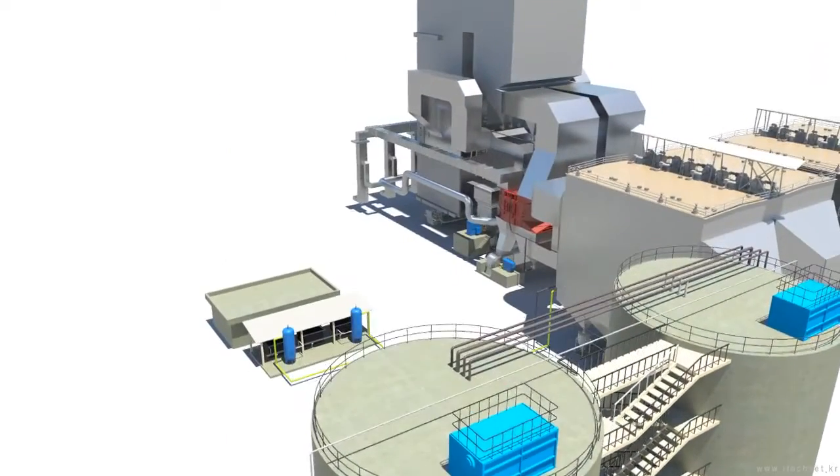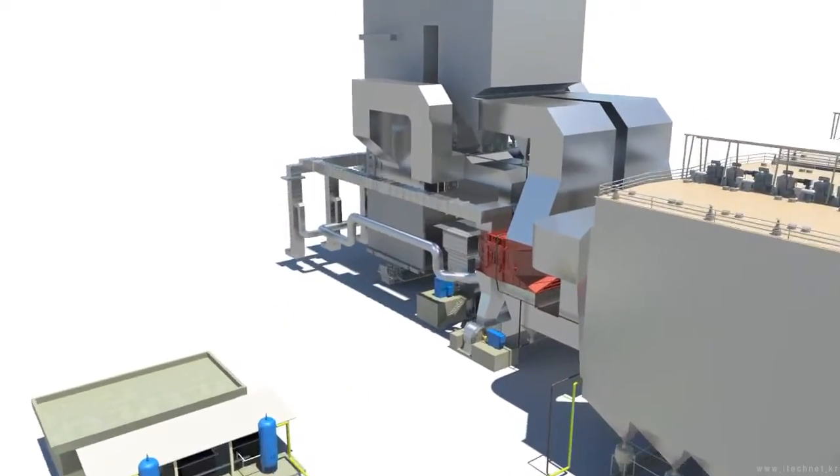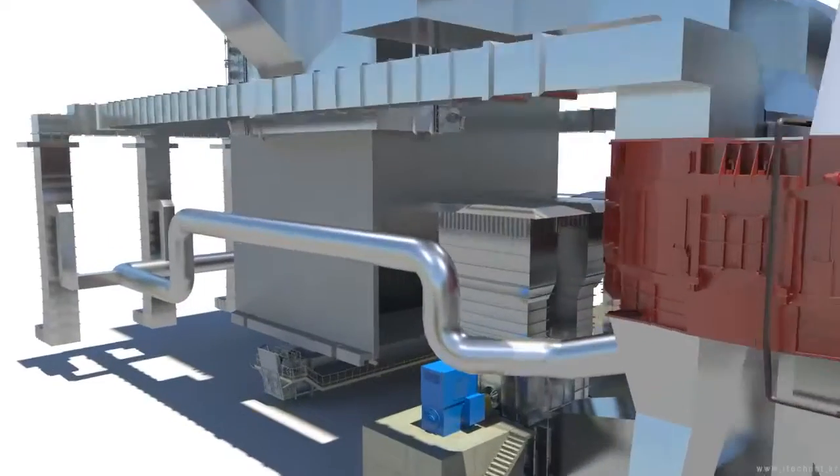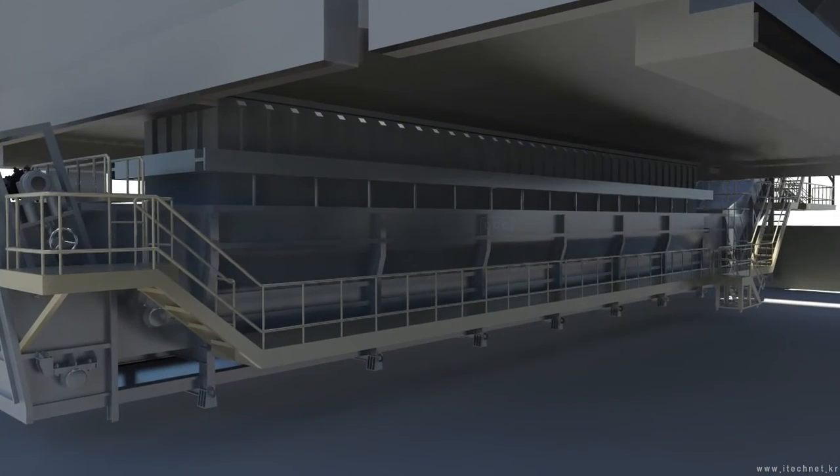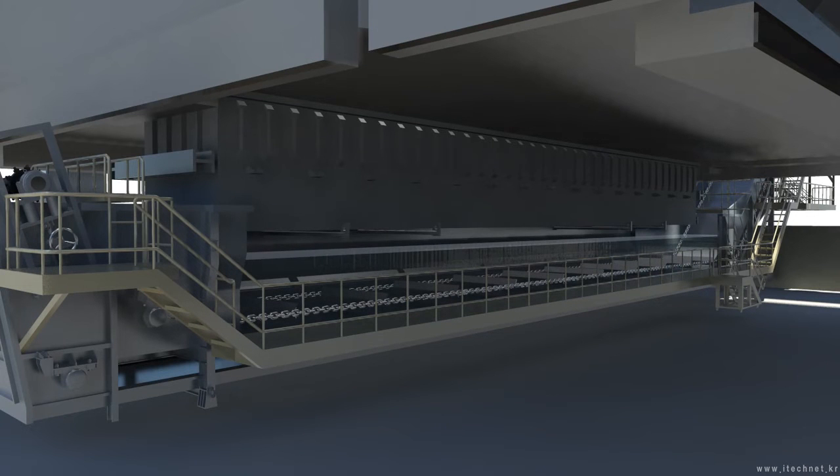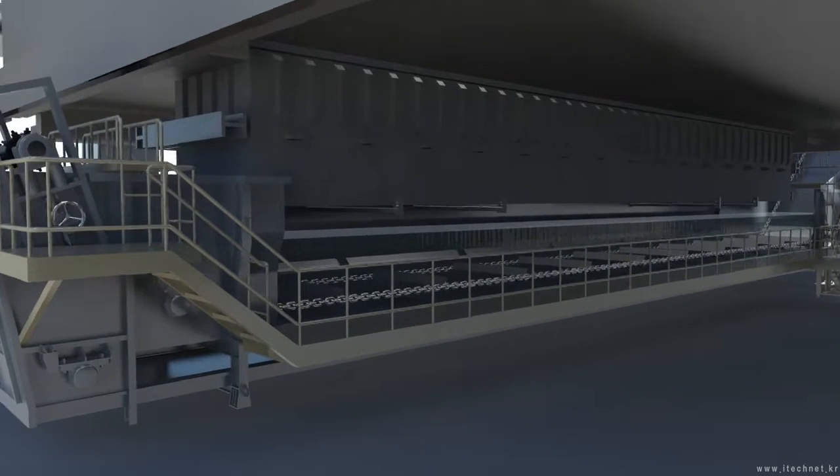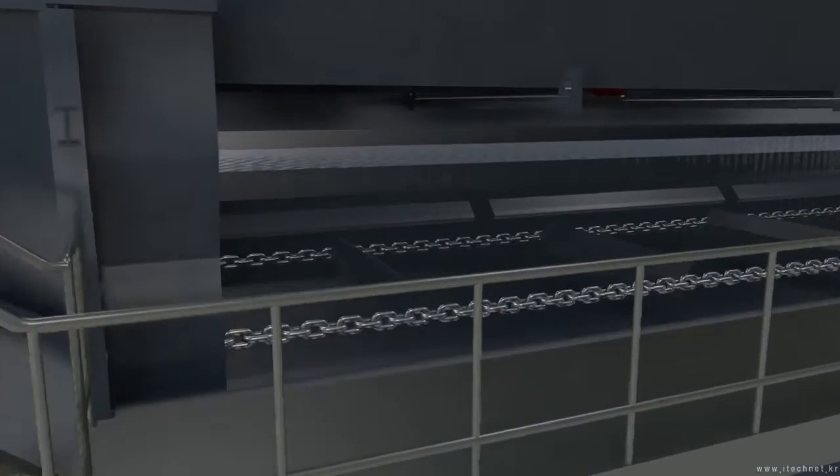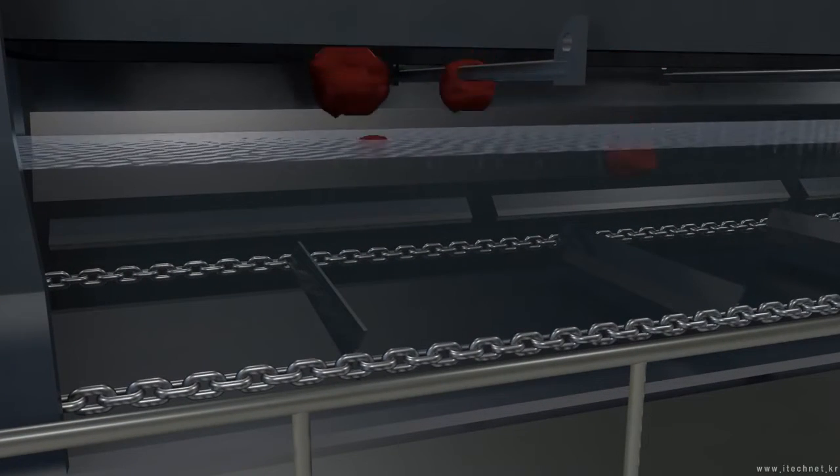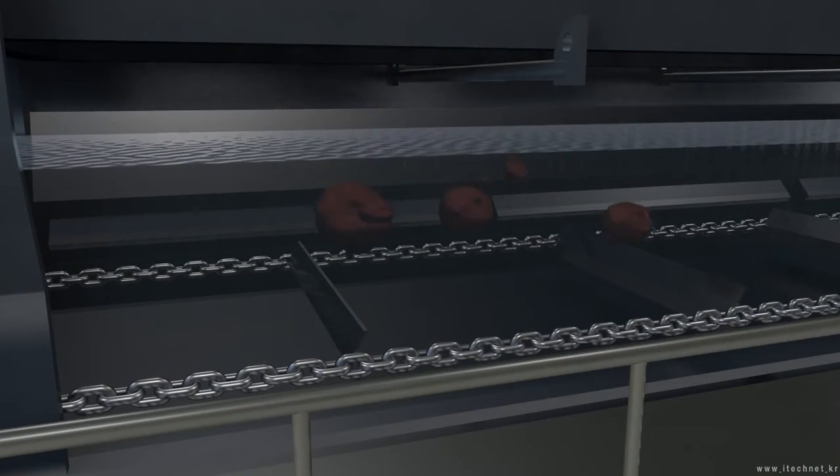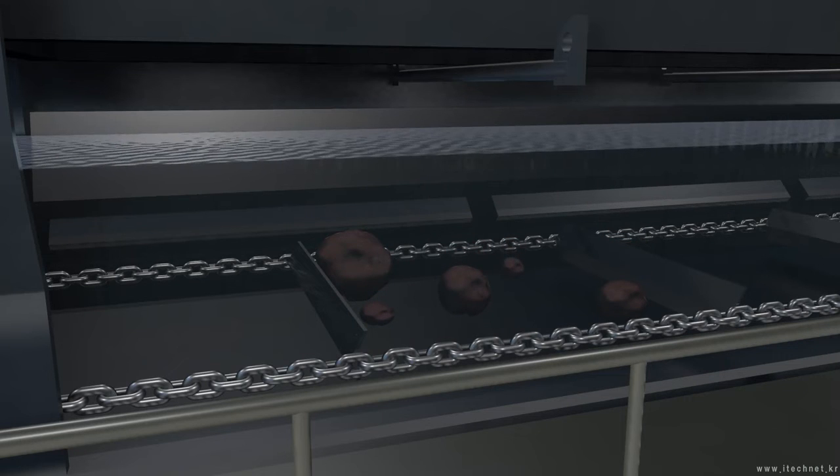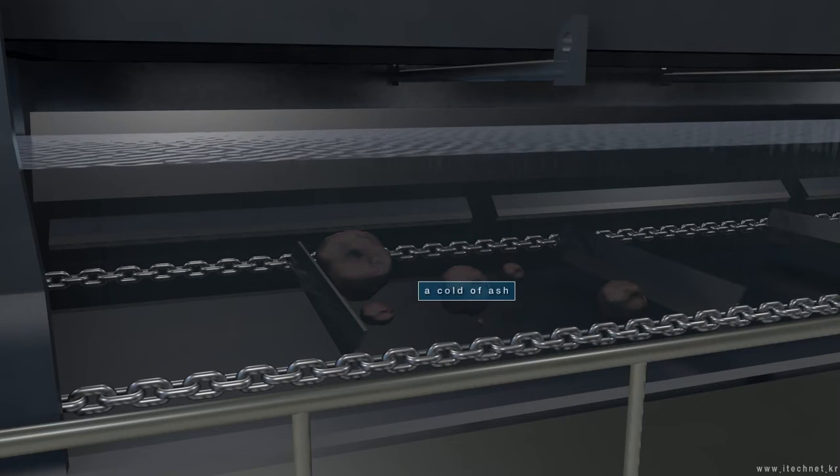The function of the bottom ash handling system is to collect, cool and crush the furnace bottom ash and deliver it to the bottom ash bunker. The upper trough of the drag chain conveyor is always filled with under 60 degrees Celsius water at a definite level. The hot bottom ash which just dropped from the boiler is being cooled when it drops to the water of the drag chain conveyor.